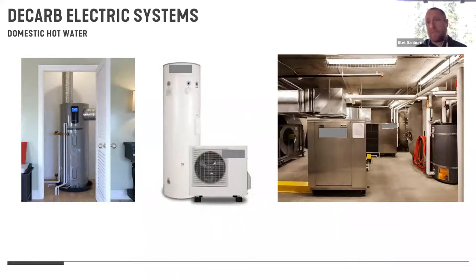The middle unit are these split type water heaters. So you have an outdoor condensing unit and an indoor storage tank. And these use a hydronic connection between the monoblock unit outside and the tank. These are available as CO2 heat pumps using CO2 as a refrigerant, and also available with more traditional refrigerants. The image on the right are some big beefy air source heat pumps with ducted outside air coming into them. And these are typically seen on some large scale multifamily projects doing centralized domestic hot water heating. I'm going to talk quite a bit more about central water heating towards the tail end of the conversation, specifically looking at some of the coordination issues and impacts around designing with heat pumps for domestic hot water.